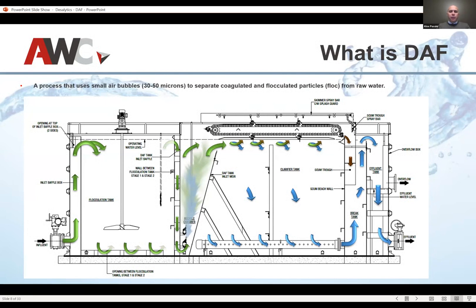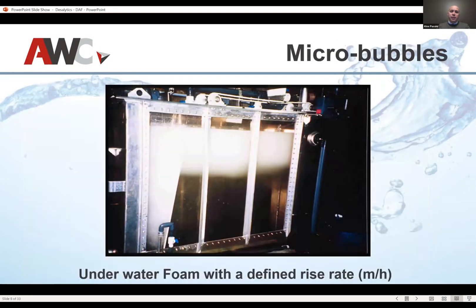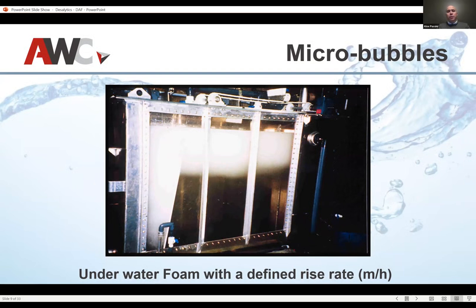Now that we understand what the technology looks like, we can start looking at applications — how things like this can either be retrofitted or put into new plants. This is a pilot plant. The visual alone gives you a better idea of how it comes through. Again, we've got flocculation ahead of this, then the saturators. The water coming through — these are all micro bubbles. It almost looks like milk or a mocha. Then you've got your skimmer rolling off the top. Key aspects to look at are your flocculation rate, your recycling rate — you are recycling water back as you create your foam — and your hydraulic loading rate going through dissolved air flotation.